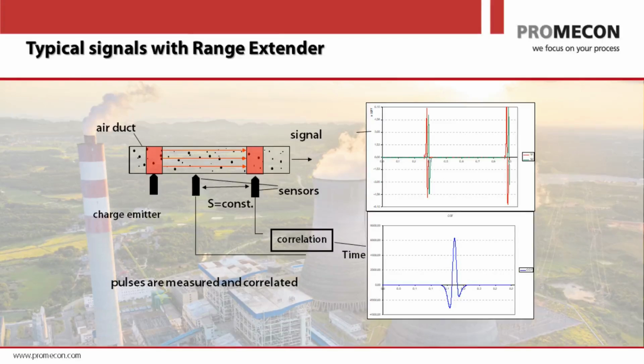So it's very hard to detect a correct pressure that you can then translate into an accurate flow. You have other measurement devices such as thermal mass flow anemometers. They have the opposite problem. Thermal flow meters are very, very good at low range. They're excellent at low range. They have a very high turn-down ratio, but also they are not linear, and they are getting very bad at high flow range. If they are a little bit dirty, or if they have a little bit of a drift problem, because they drift, their major drift is at the high end.